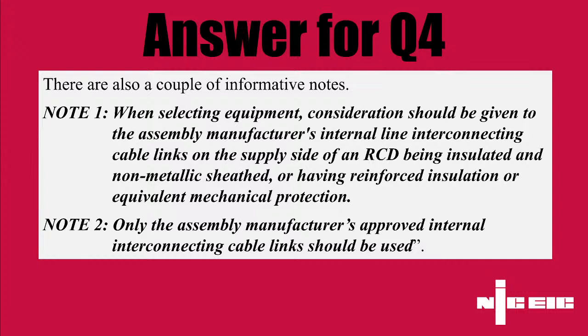But I think generally, though, you find a lot of it would be just transferred over to comparisons with the current regulations as a C3 for that reason, and that's why we would say improvement recommended. It's not saying it's got to be done. It's not saying it's unsafe. It's just saying it's an improvement to bring it up to the current standard, because otherwise, if it was to supersede the new regulations, you'd be saying that all the old regulations would be unsafe, and that's not what it's saying, and that's why it does say the C3 of improvement recommended. It's just saying you can improve it to bring it up to current standards, basically, but it's not unsafe in its current form, basically. Yeah, absolutely.